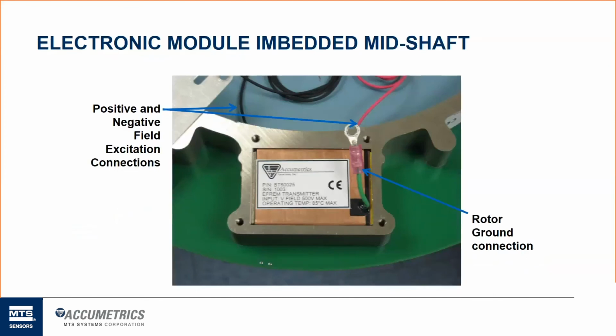This is the electronic module that's embedded in the steel collar itself. We have to make connection to rotor ground. So as I was explaining before, the process to accurately measure the field resistance and field voltage, we have to make contact to the negative side and the positive side of the field, as well as rotor ground. So we use the steel collar itself to get that rotor ground connection. So that has to get mounted directly to the shaft, a very tight fitting application, so that that's a reliable electronic ground connection. And then on the other side is where the positive and negative leads run off onto the board itself and make that contact. And we'll go into a little more detail on that.